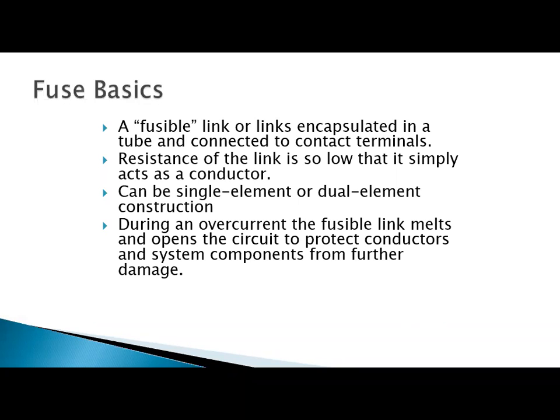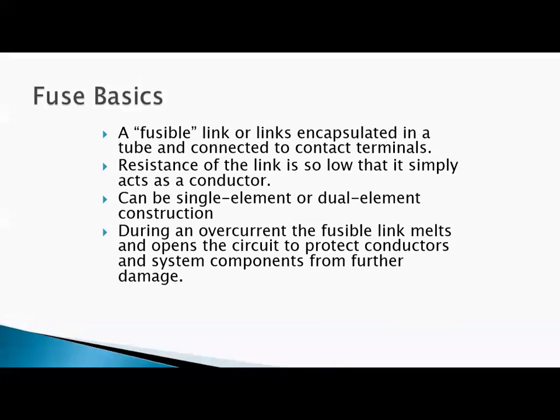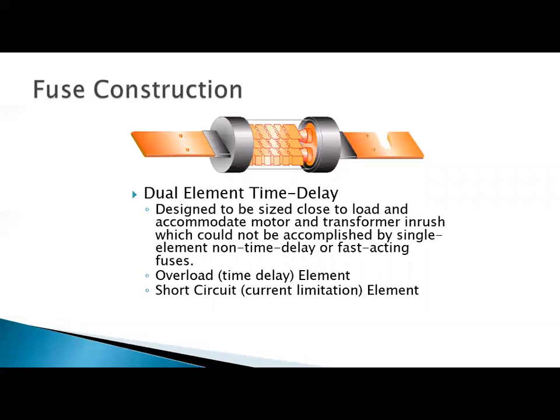And these can be single element or dual element. They're going to have a fusible link that can melt and open the circuit and protect whatever we have. So on a dual element, a lot of times we'll use these on motors or transformers that have coils inside and have a large inrush current. We want to make sure we allow the motor to start. And so we'll allow a higher current to go through for a specified time, and then we're going to go ahead and protect it after we have timed out.